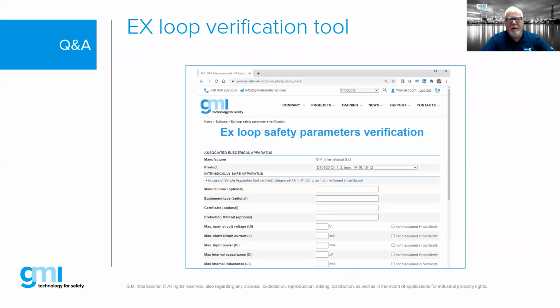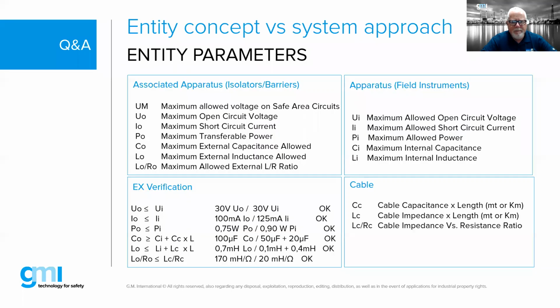Mauro, if you go back one slide to the EX verification, that's the key thing we need to know. We need to check all those parameters to make sure the associated apparatus and cable are acceptable to the field device based upon the gas groups.